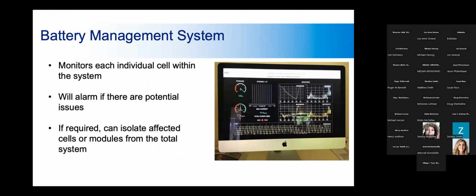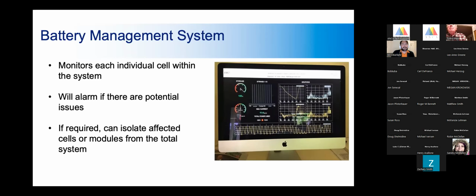Got some more components of these systems. In addition to cells, modules, and racks, we have the battery management system. That's the eyes, ears, and brain of the system. It monitors each individual cell within the system, and has the ability to send an alarm if there's an irregularity or potential issue within the cell. In addition to sounding an alarm, certain battery management systems are also capable of isolating the problem area of the system.